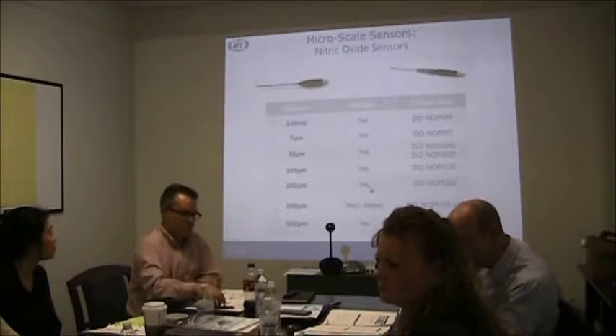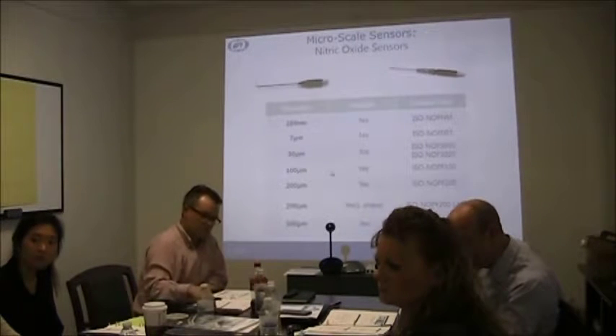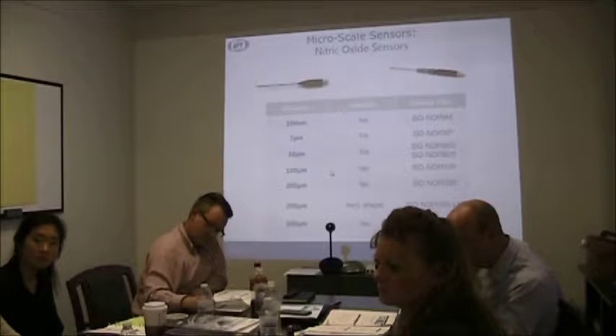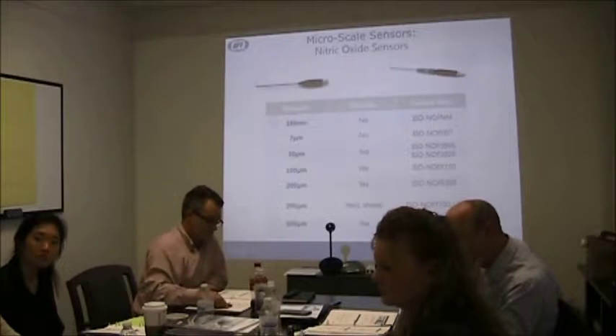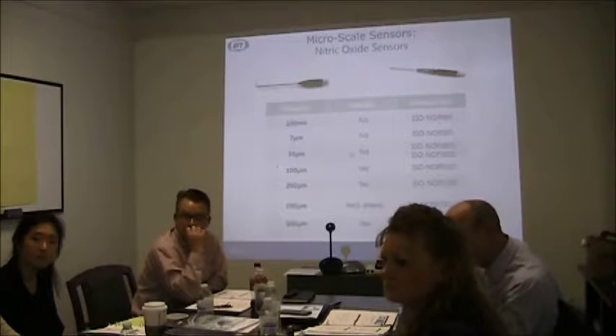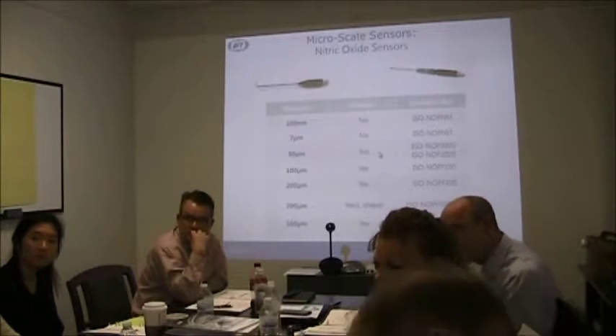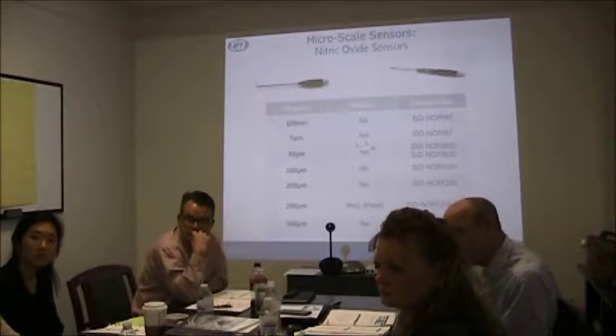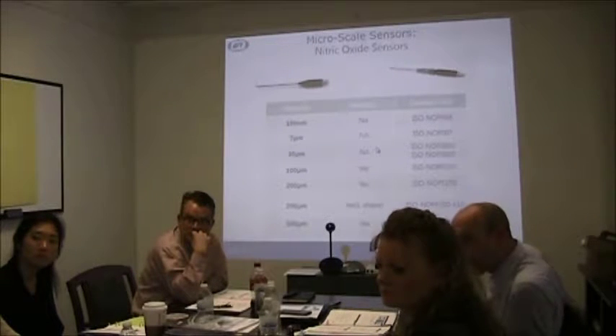All the sensors behave just like a battery would. They're not indeterminate, with forever shelf life. As you use the sensor, it's going to deteriorate in terms of performance over time. So when you ask whether oxygen is being consumed, yes, at the surface you're actually seeing a degradation in the reference and counter electrode performance because of the oxygen reacting. So that's what happens to the sensor itself.